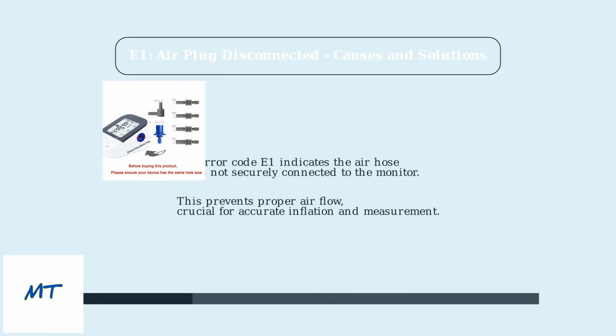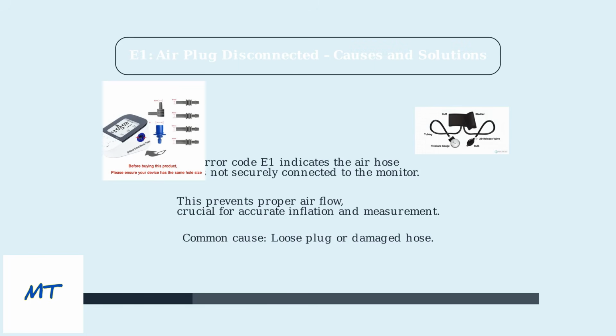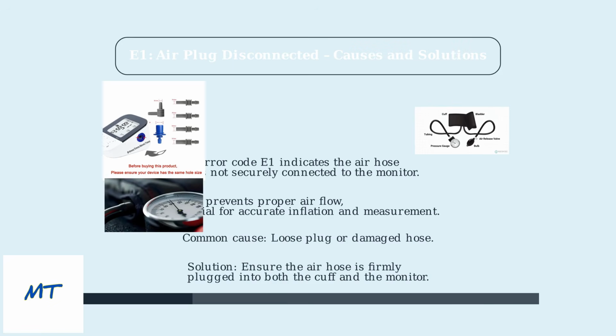Error code E1 indicates the air hose is not securely connected to the monitor. This prevents proper airflow, which is crucial for accurate inflation and measurement. The most common cause is a loose plug or damaged hose. To fix it, ensure the air hose is firmly plugged into both the cuff and the monitor. If the hose is damaged, replacement is necessary.